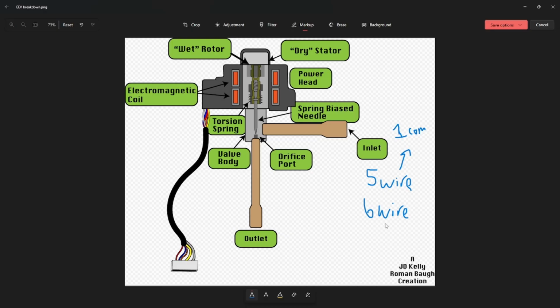The 6-wire variants have 2 common wires. Most of the Trane units and the TAM air handlers will use the 6-wire variant. With Trane, brown and red are your common wires, which is backwards from what you normally think, because normally we don't associate red with common, but those are the colors of Trane's stepper motor.